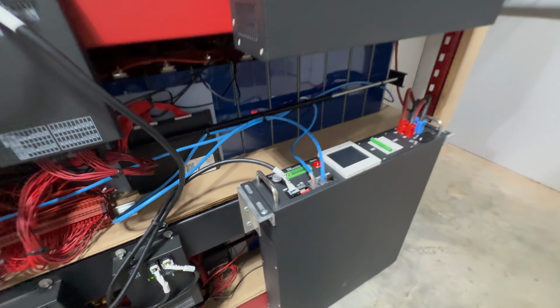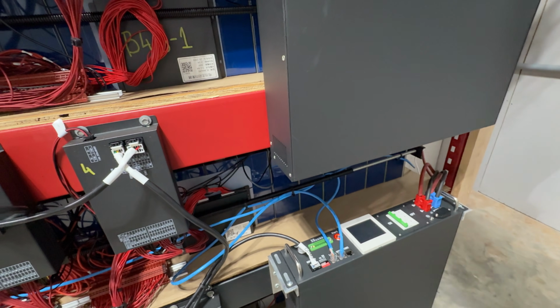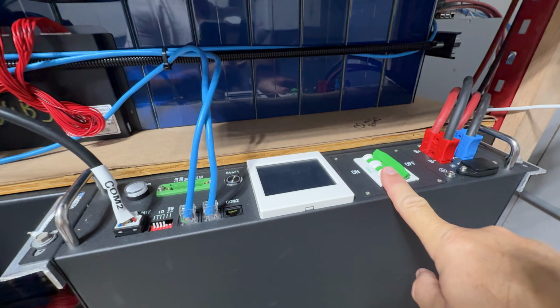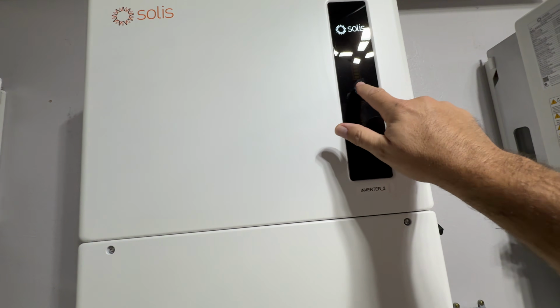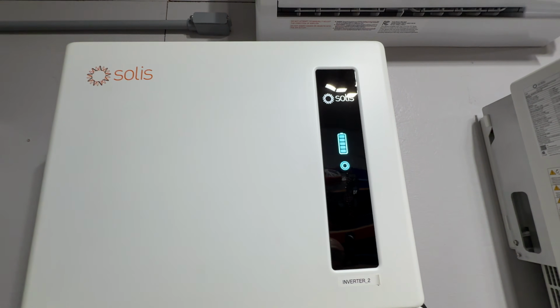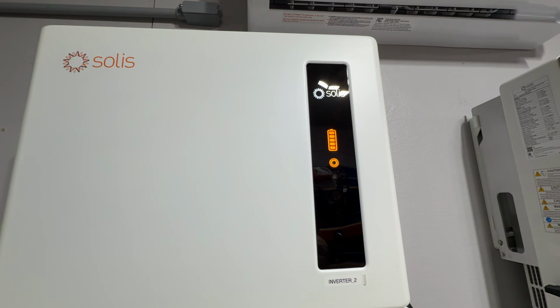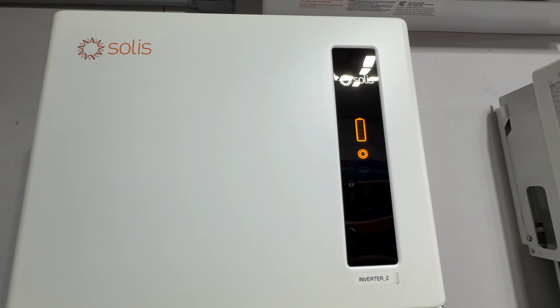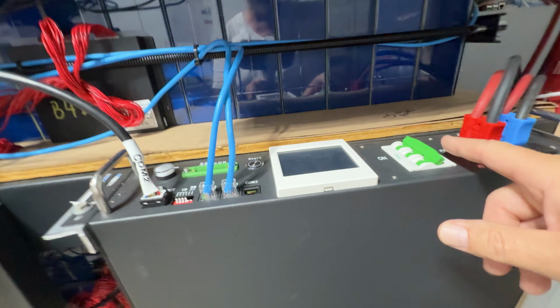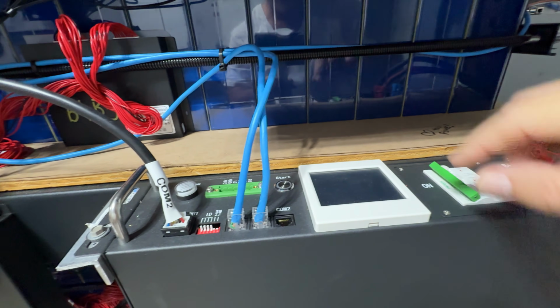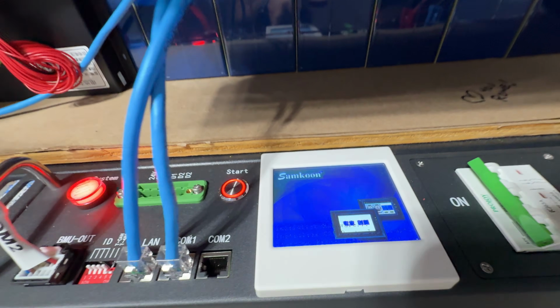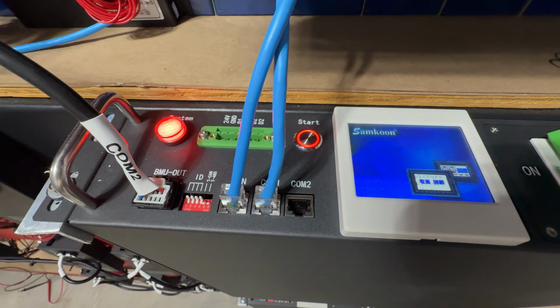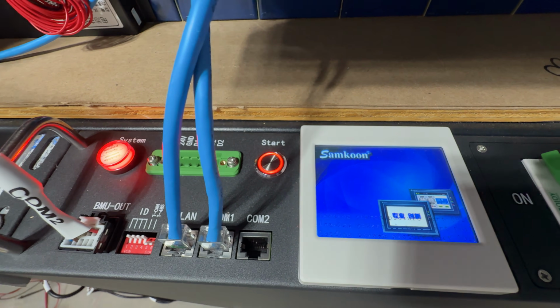Let's go to a different BMS and simulate the startup. I turned it off - this is for inverter 2. Inverter 2 will soon go yellow once it registers a communication loss. There it is, it clicked yellow. It says it doesn't see the battery, doesn't see communication. Now what we're gonna do is turn this on, click, and it will start up, going through a self-test right now.